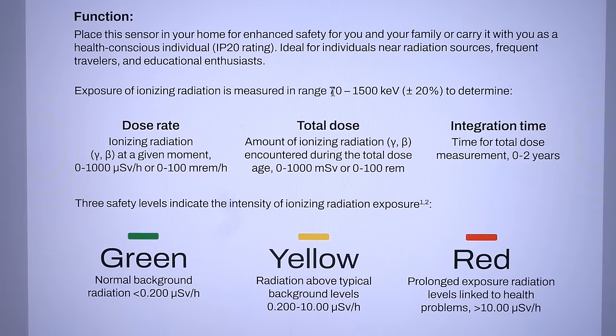It works from 70 to 1500 kiloelectronvolts, plus minus 20%. It measures the dose rate and the accumulated total dose. And it shows green under 0.2 microsieverts per hour, yellow from 0.2 to 10 microsieverts per hour, and red for over 10 microsieverts per hour.